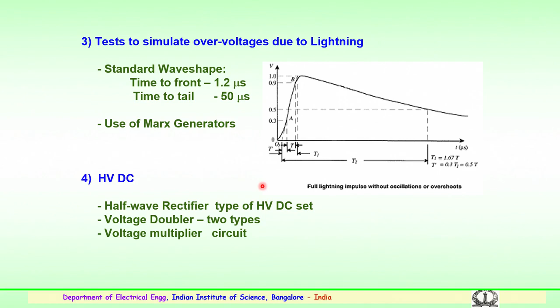So general tests which are conducted in the lab for the insulation are the voltage withstand test. Again the voltage withstand, it is the AC voltage, or it could be the DC voltage withstand where the equipment or the insulation is of DC. Impulse is again the surges for both lightning and switching. These lightning and switching surges are generally carried out for two conditions, that is the dry and wet conditions. For the dry conditions, the specified values for particular voltage levels are given, and the wet conditions you simulate using a nozzle set. Artificial rain nozzles are used to simulate the rain conditions, and the switching surges or lightning surges are applied, or the AC voltage or the DC voltage is applied, and whether they will be able to withstand or the flashover of these are studied.